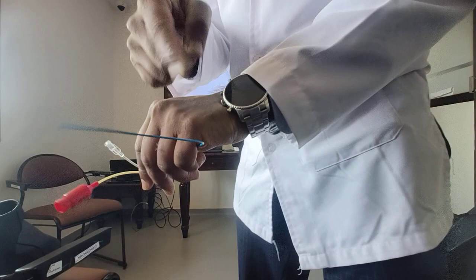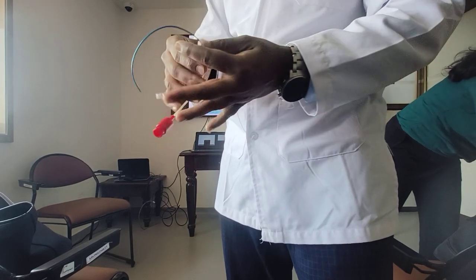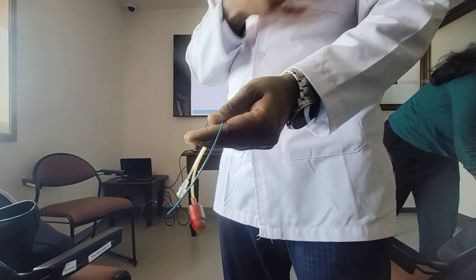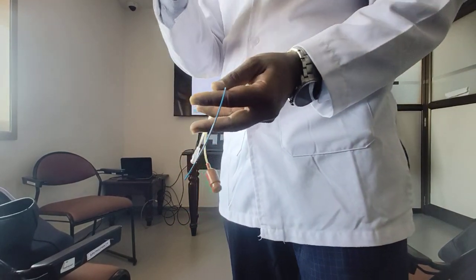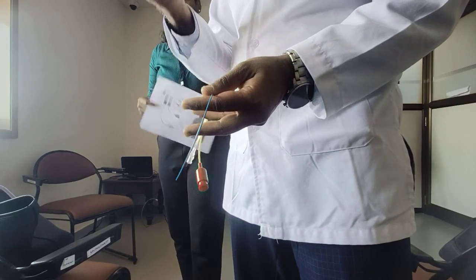So I'll just show it to you. You can see this is the catheter, and there is a radial one also. This is femoral. The radial one is 40 centimeters long, so it will be longer, but of course we don't want to risk vascular injury and all this. But you can put radial also with the PiCCO. This is the difference from the EV1000: you can't use radial there.